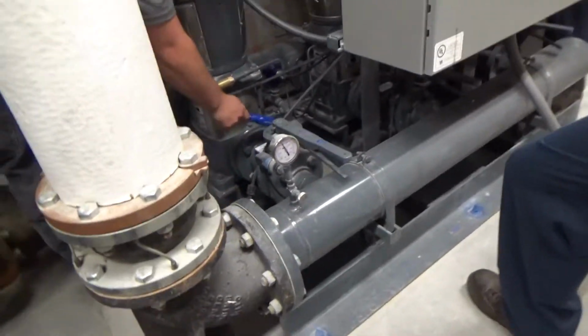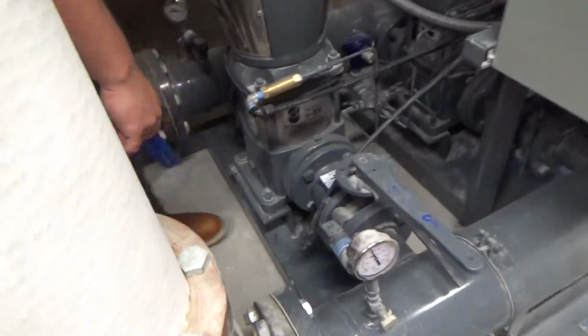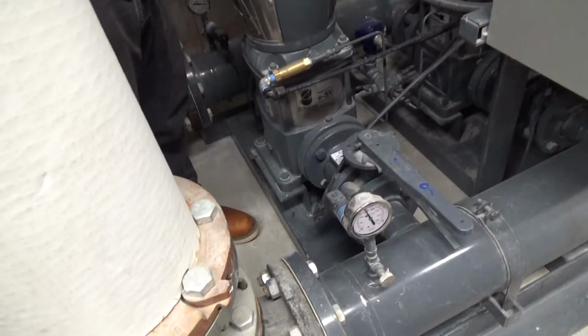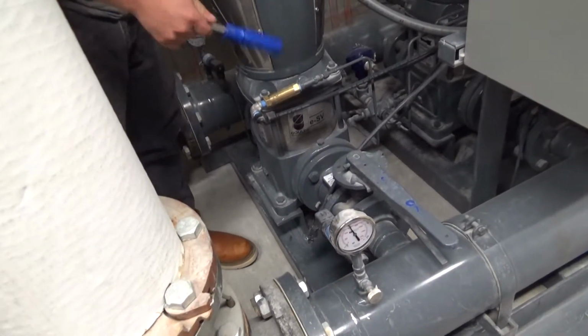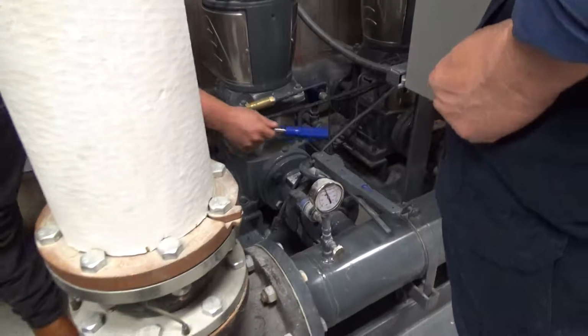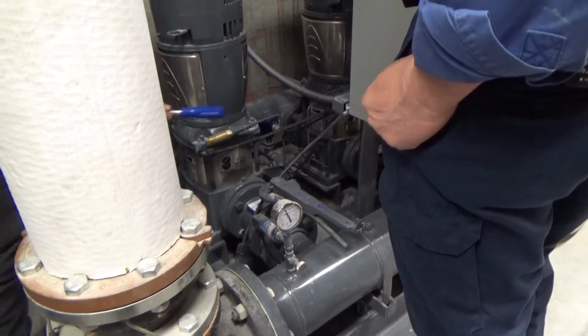There is a check valve right here, so if you guys are ever having issues with equalizing suction to discharge, that check valve might be stuck open and might need to be pulled apart and cleaned out. And again, you would just isolate it on the 2 valves, and you would actually isolate it down here also.